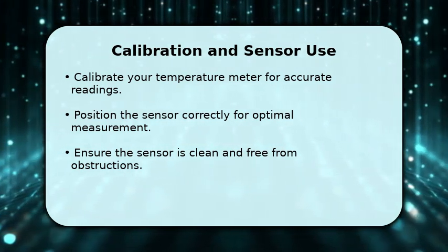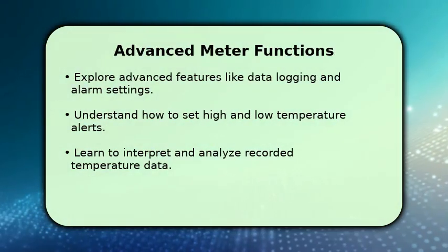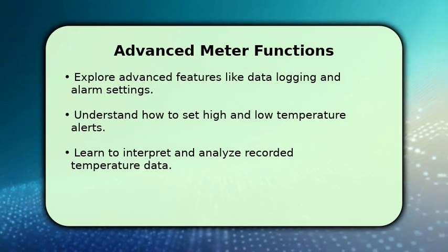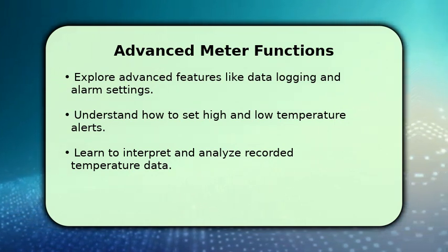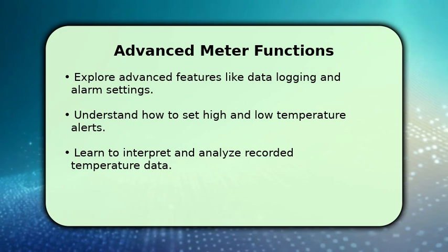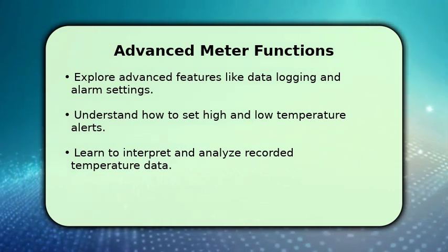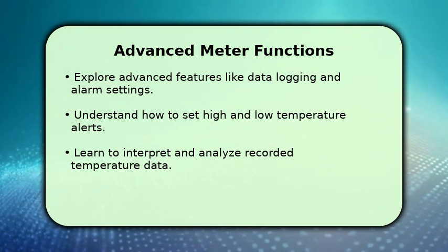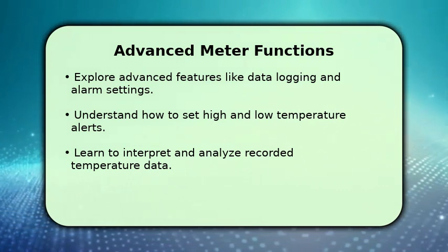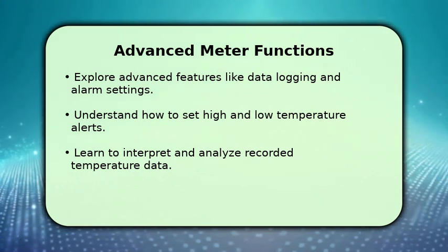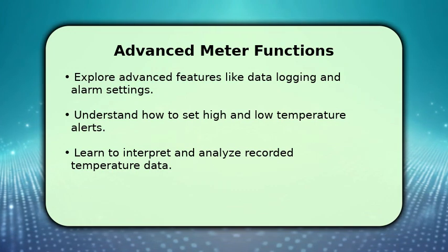for reliable data. Many modern temperature meters offer advanced features that can greatly enhance your monitoring capabilities. We'll explore functions like data logging, which allows you to record measurements over time, and how to set up custom alarm thresholds. You can program your meter to alert you if temperatures exceed a high limit or drop below a low limit, providing crucial real-time feedback for critical applications.